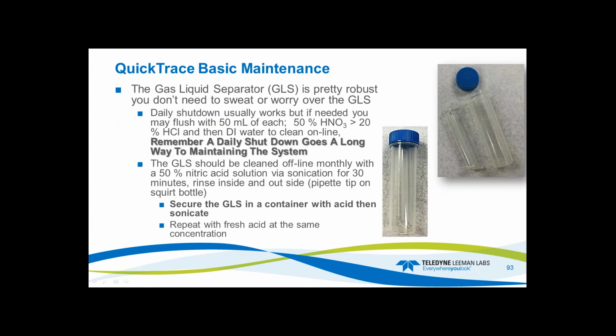Some basic maintenance. The gas liquid separator is pretty robust. Don't sweat it. Usually the daily startup and shutdown will take care of it, but if you need an additional online cleaning, you can use 50% nitric. 50 mils of that, followed by 20 mils of HCl and 20 mils of DI water. But remember, again, daily cleaning, startup, and proper shutdown goes a long way.